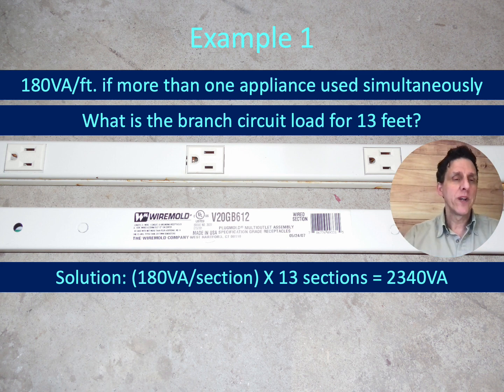In any case, 180 volt amps per section times 13 sections. That math works out to 2,340 volt amps. Okay, that's the calculated load.